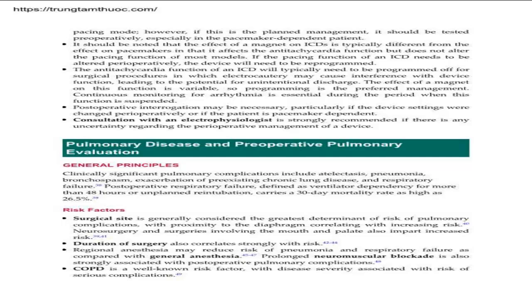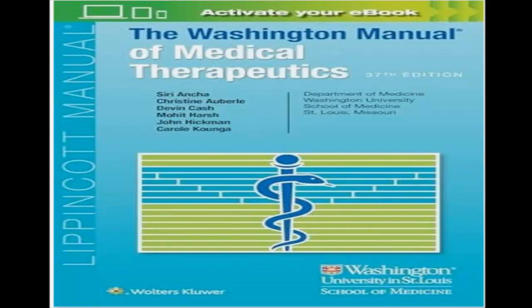The antitachycardia function of an ICD will typically need to be programmed off for surgical procedures in which electrocautery may cause interference with device function, leading to the potential for unintentional discharge. The effect of a magnet on this function is variable, so programming is the preferred management. Continuous monitoring for arrhythmia is essential during the period when this function is suspended.